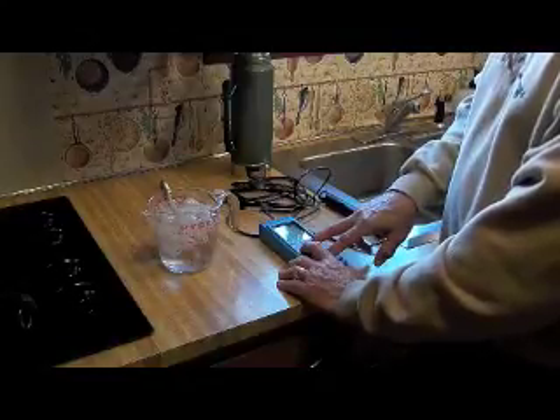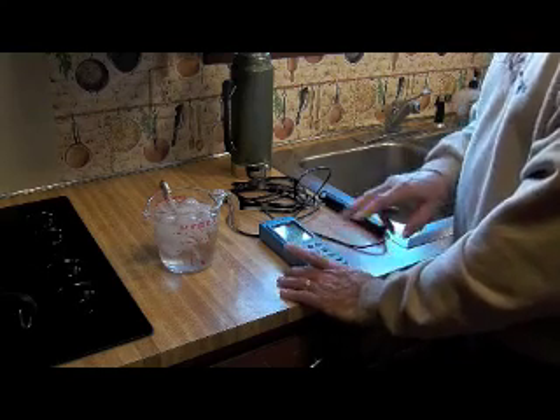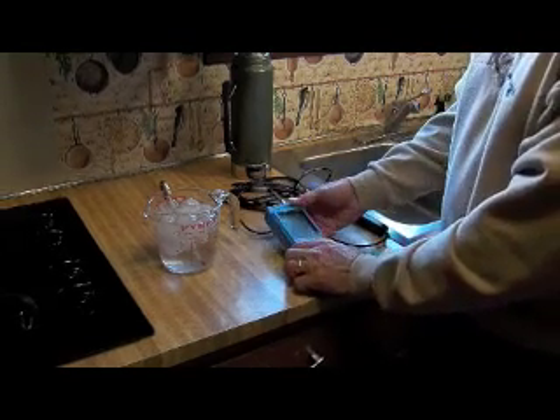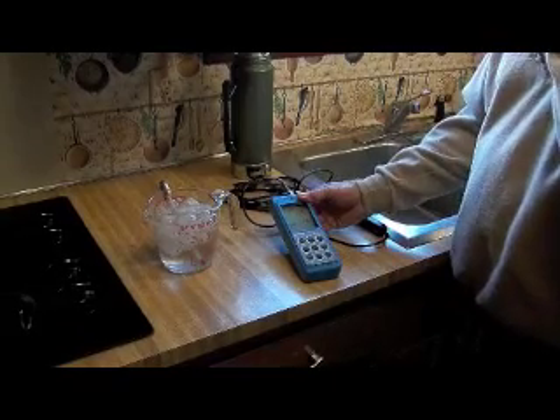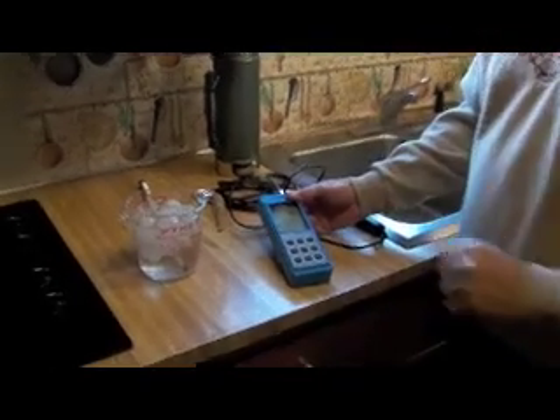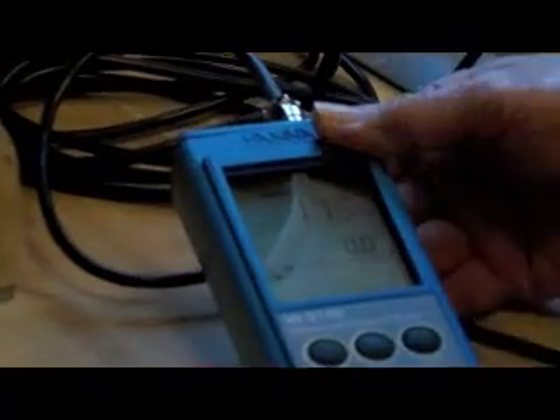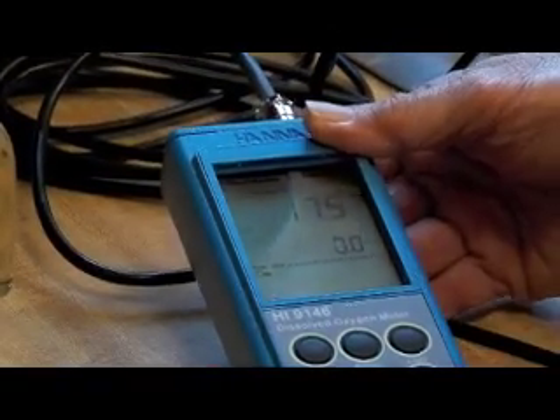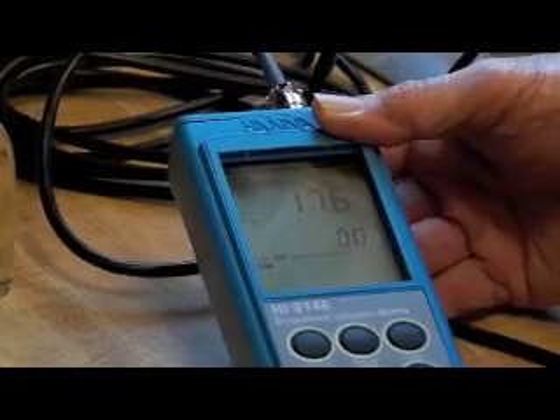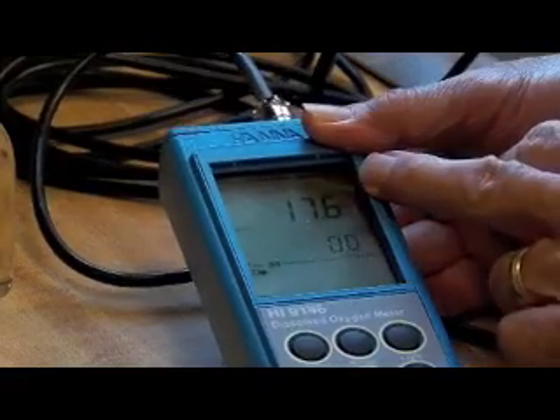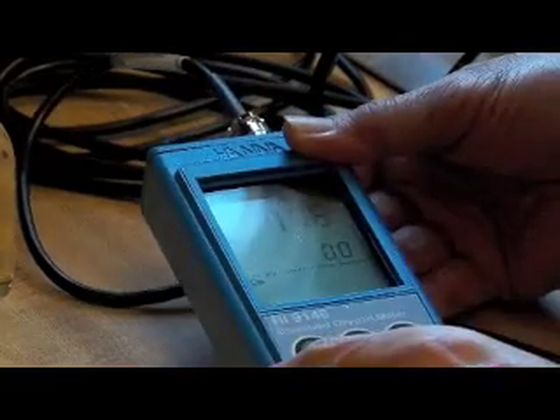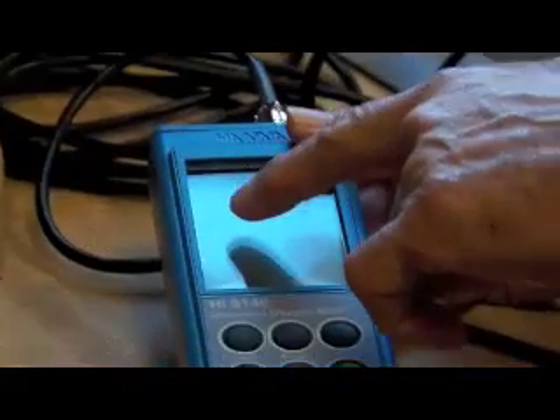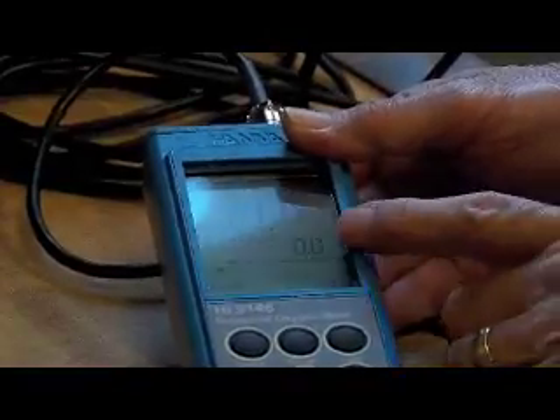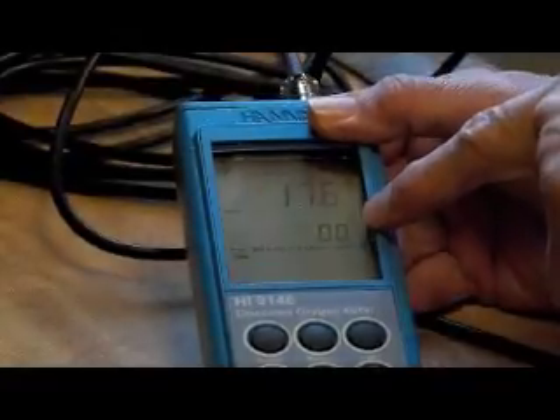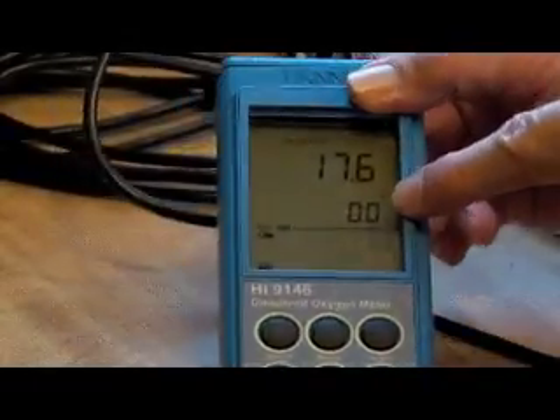and you'll get 100% battery, and then the screen you should be reading rather than the condition. If you remember when we turned it on without hitting these extra buttons, you got that condition where the meter was conditioning itself. Well, now you have calibration written on the top, and there's a temperature. You actually have a temperature here, and I'm getting a wrong flashing on the screen, and that's because what it's looking for is a temperature close to 0 degrees C at this point. And that's what you should look for.